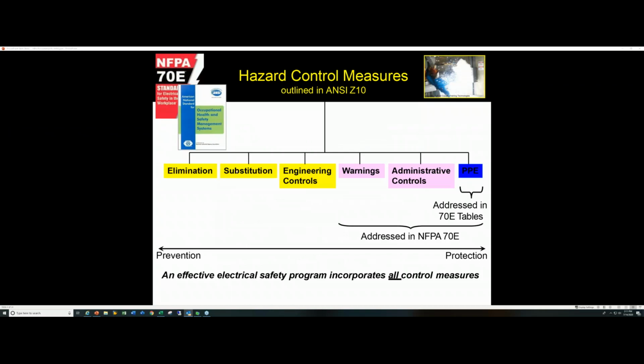So here's a different look at it, and that's what 70E does, as well as the ANSI standards. Elimination, substitution, and engineering controls are your top tiers, and then your lower tiers here. And where are they addressed? Well, PPE is addressed in the 70E tables, and NFPA 70E addresses basically your warnings, your admin controls, and your PPE. What it doesn't really address is the elimination, substitution, and your engineering, your design.